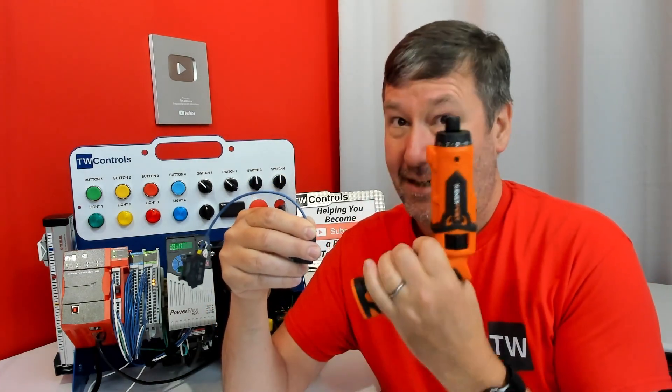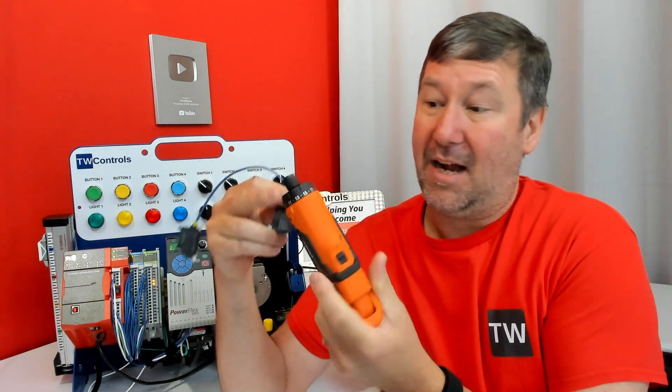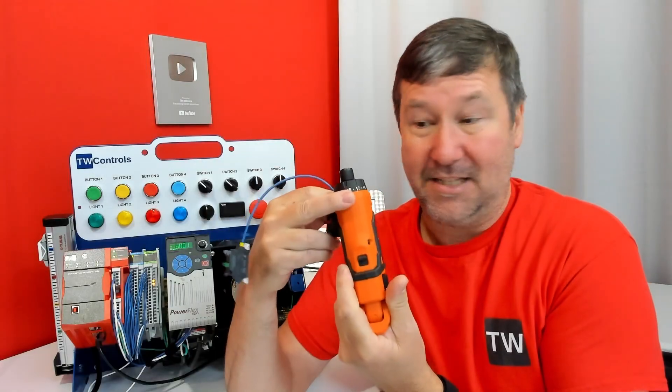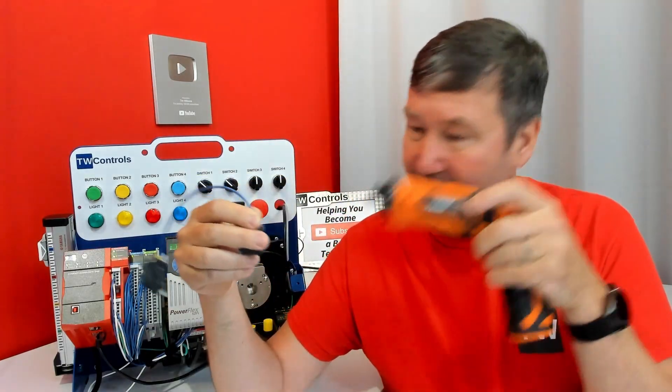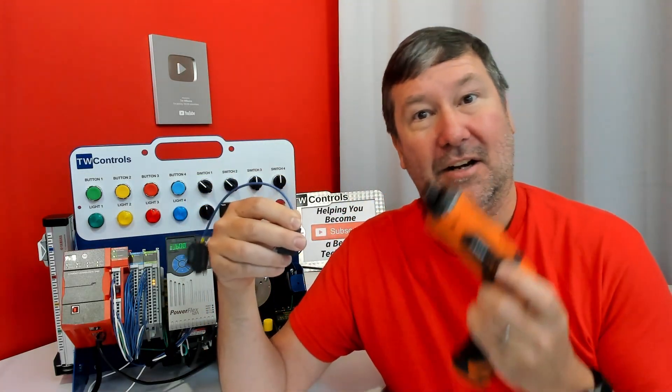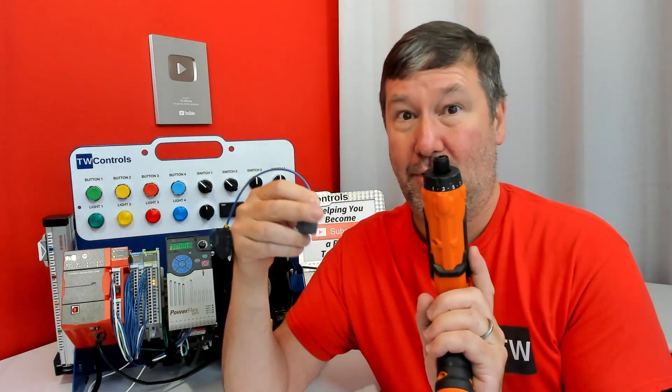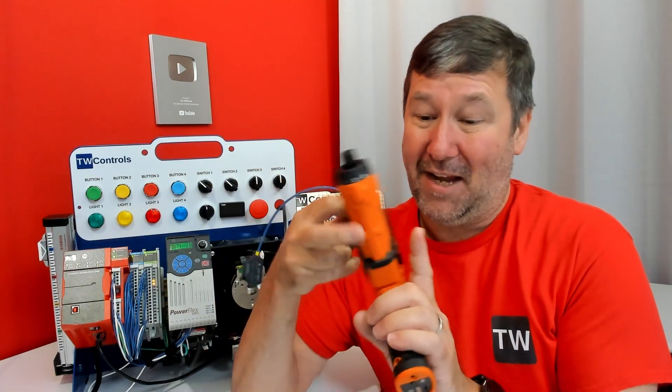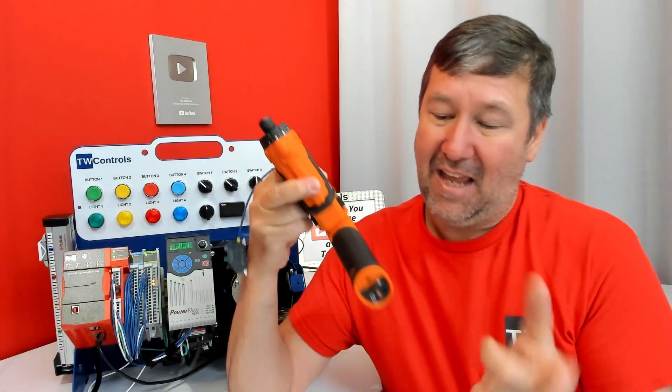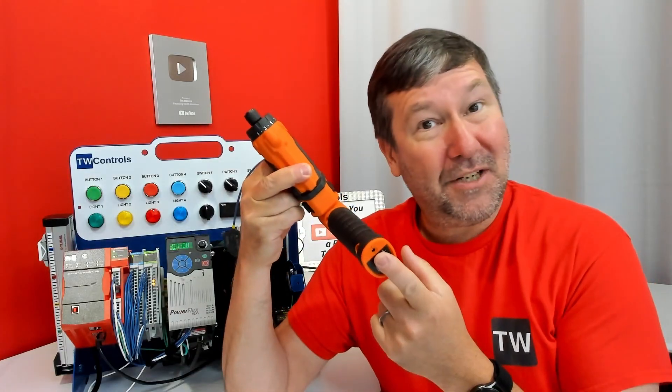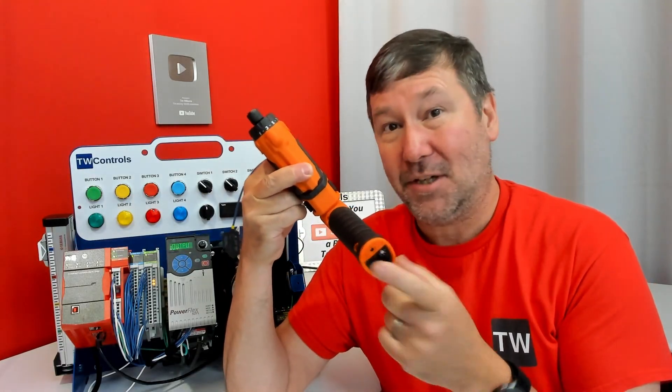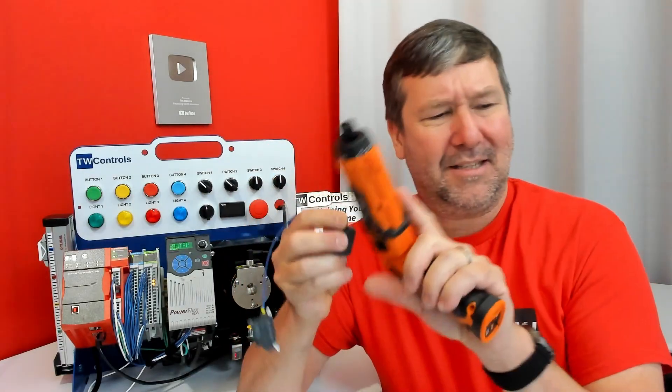Now when we say torque, that does not mean we're using an electric torque driver that has the inch-pound settings on it. Zooming in on it, this is not UL approved. One, it has no calibration, and two, we don't know how good the battery is.